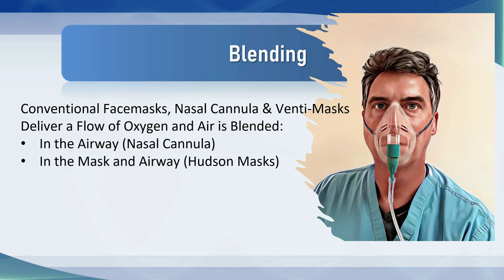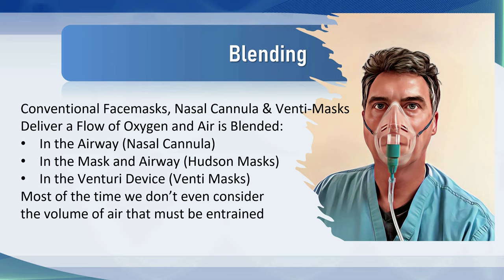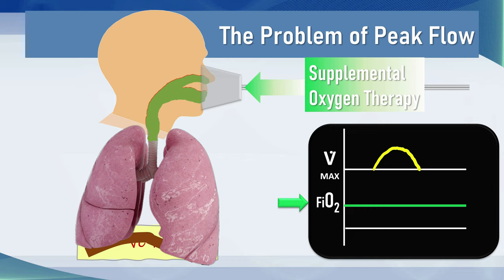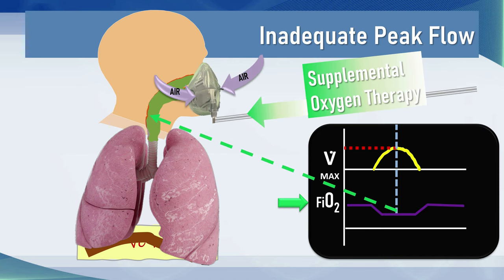Most of the time we don't consider the volume of air that must be entrained, but air must be entrained — if you're giving 40% oxygen, the remaining 60% the patient receives is nitrogen. It's really important that you know the volume of air and total flow because of the problem of peak flow. When the patient takes a breath, their peak flow must be matched by an FiO2 that stays stable. If it doesn't, the patient entrains more air during a big breath, the inspired oxygen tension drops, and this is hugely problematic.